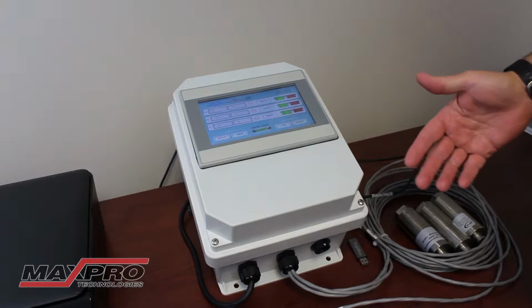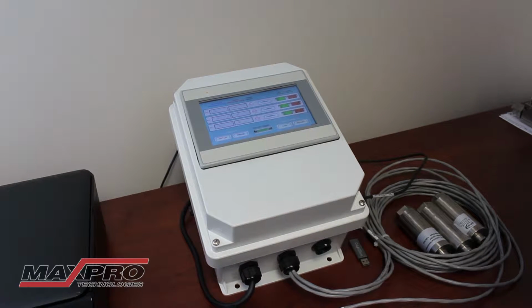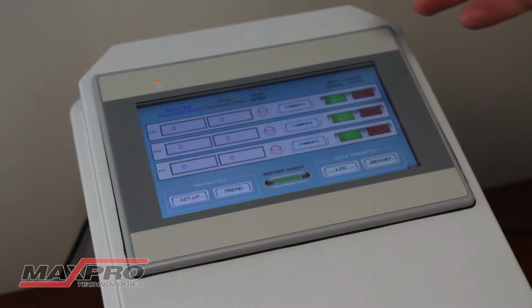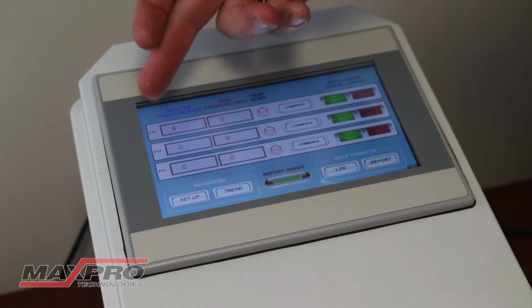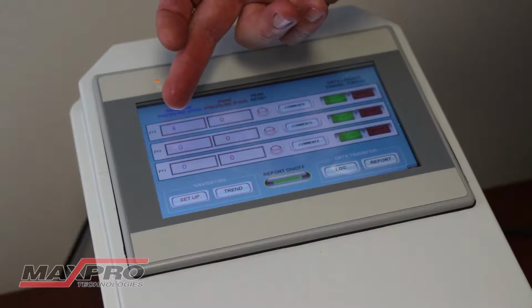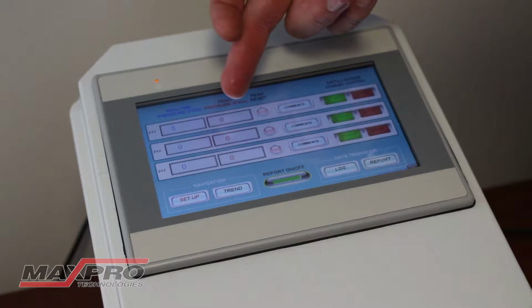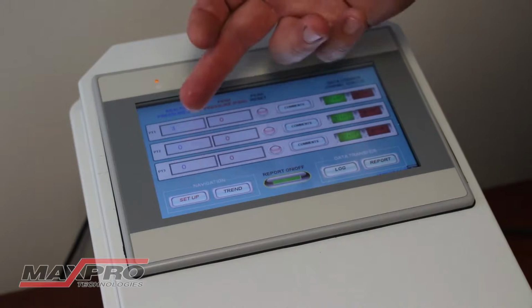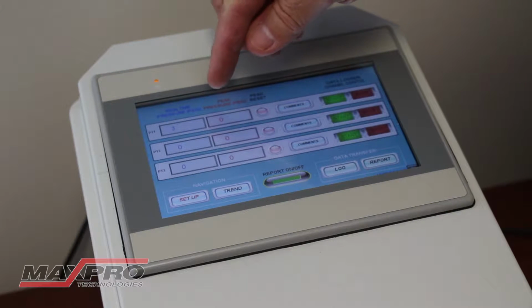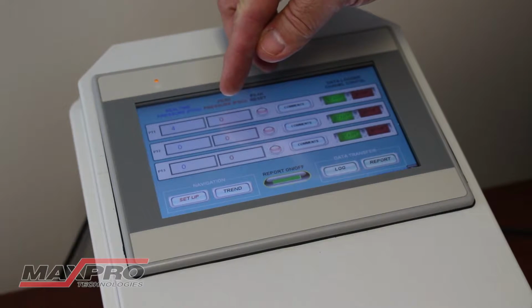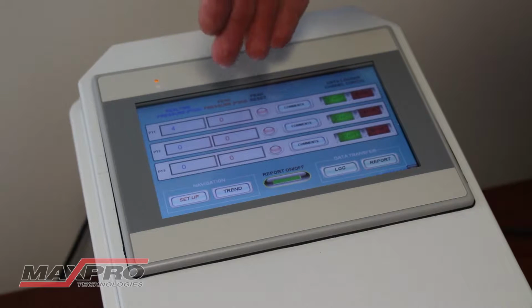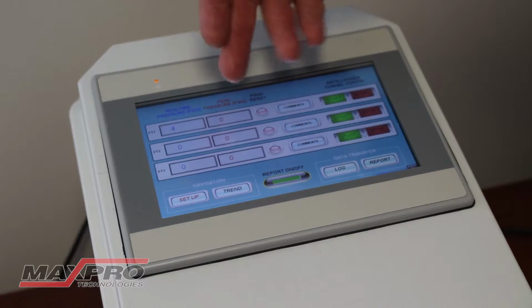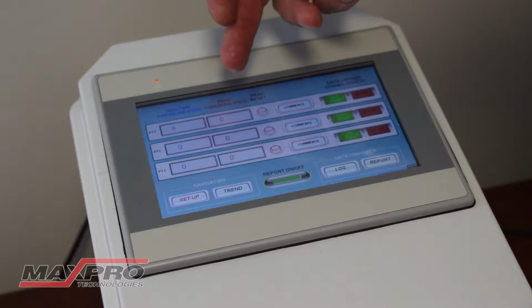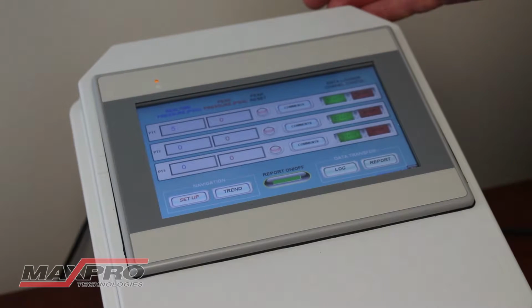We have a single channel. We've done all the way up to a 10-channel pressure logger. Okay, this unit has 3 pressure transducers, so we have real-time pressure here, peak pressure for the 3 different transducers. The peak pressure gives you the highest pressure that transducer has seen, so if you have a pressure drop or a leak in your system, you can see the difference between the peak pressure and the real-time pressure.